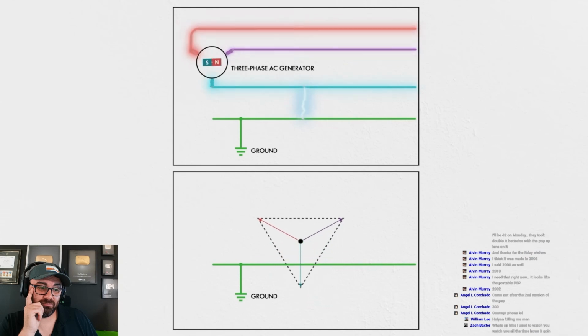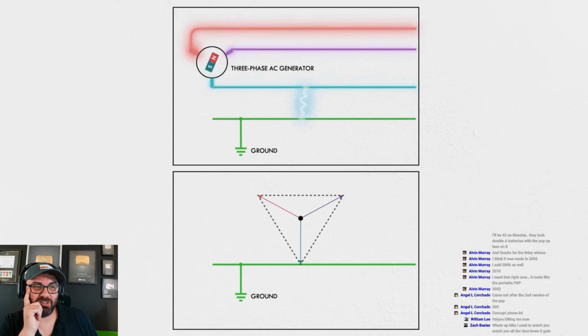Now, all of a sudden, that weak coupling force keeping the phase to ground voltages balanced is overpowered, and all the phases experience a voltage shift with respect to the ground. But the phase-to-phase voltages don't change. In fact, a ground fault on an ungrounded power system usually doesn't cause any immediate problems. The motors and transformers and other loads on the system don't really care about the phase to ground voltage because they're hooked up between phases. This is one benefit of an ungrounded power system. In many cases, it can keep working even during a ground fault. But of course, there are some downsides too.